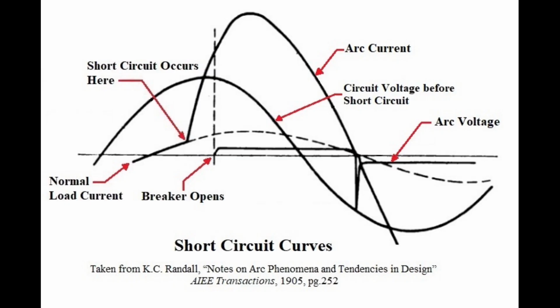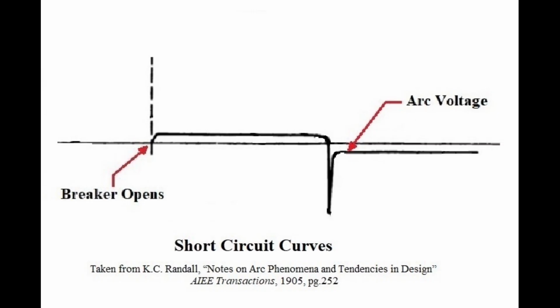Without any means of recording this less than one cycle event, the engineer of that time had no idea of the details of the fault current. What form the fault current took was difficult to determine. The shape of the arc voltage curve gives us an idea of how complex the voltage wave is. In general, the more the current deviates from a sine wave, the greater the magnitude of the high-frequency harmonics it contains.